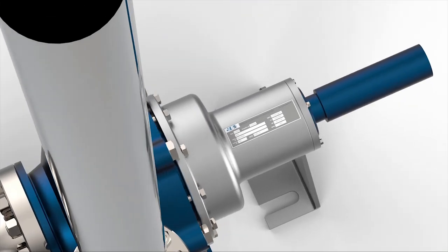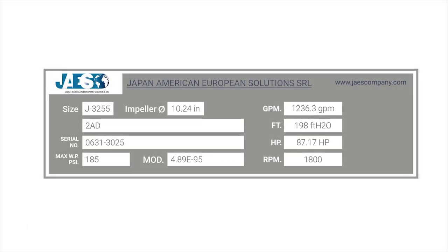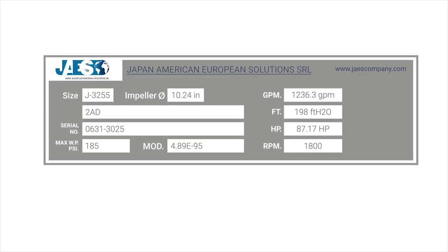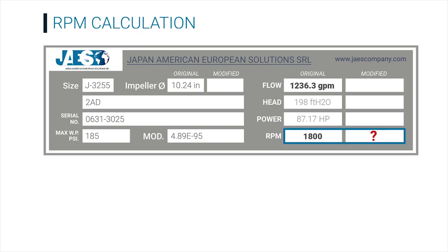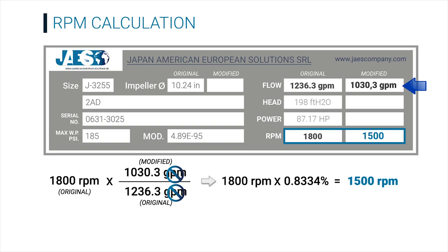Let's try now to modify some of these parameters and calculate the results. Remember that these calculations will only provide us with theoretical values — the actual performance of the pump could in fact be slightly different. The first value we are going to calculate is the RPM of the pump: what RPM do we need if we want to change the original flow rate? The new RPM value is equal to the original RPM multiplied by the division between the modified flow rate and the original flow rate. Following the calculations, we cancel out the gallons per minute and find the ratio that, multiplied by the original RPM, results in 1500 RPM — the rotation speed the impeller must reach to meet the new flow rate.